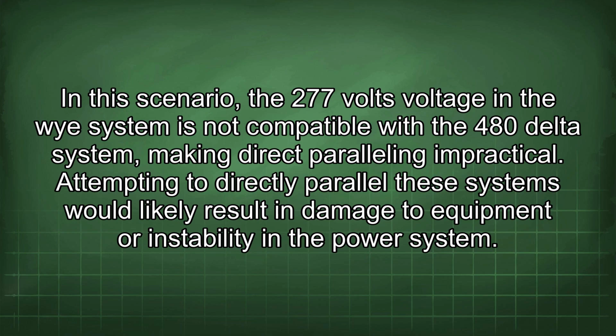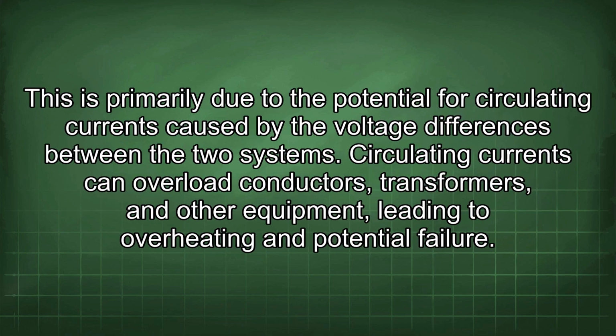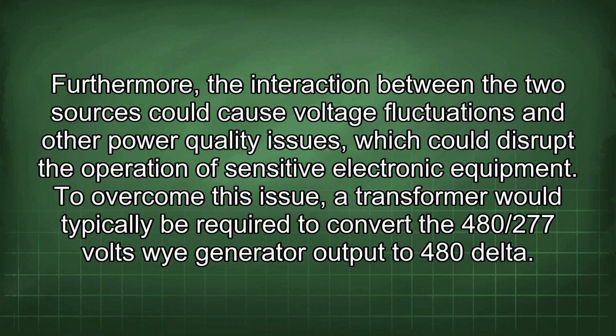power system. This is primarily due to the potential for circulating currents caused by the voltage differences between the two systems. Circulating currents can overload conductors, transformers, and other equipment, leading to overheating and potential failure. Furthermore, the interaction between the two sources could cause voltage fluctuations and other power quality issues, which could disrupt the operation of sensitive electronic equipment. To overcome this issue, a transformer would typically be required to convert the 480/277 volts wye generator output to 480 delta.